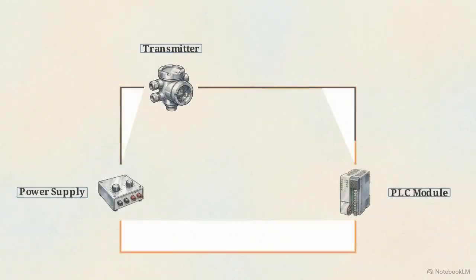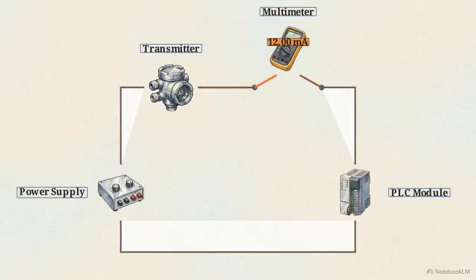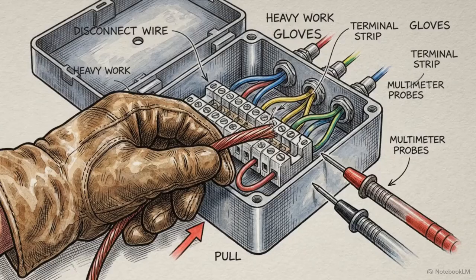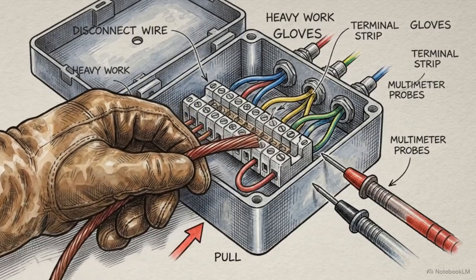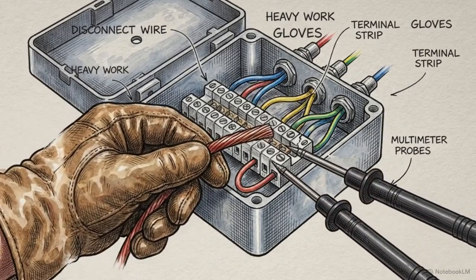To measure electrical current with a standard digital multimeter, you have to insert your meter in series with the circuit. But physically breaking the wire in the field to attach those multimeter probes instantly drops the entire loop current to zero. That momentary disconnection is instantly detected by the controller as a fault, triggering the exact plant shutdowns the live zero was designed to execute. The solution is a non-invasive hardware bypass.